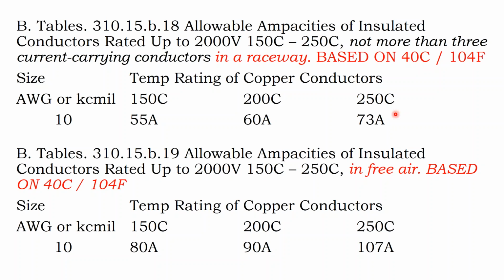It just so happens that a lot of solar equipment is designed to accommodate up to a number 10 cable, and solar modules are outputting around 8 amps. And so often up on the rooftop, for a variety of reasons, you're using number 10 cable on the roof for your solar module to solar module connections.